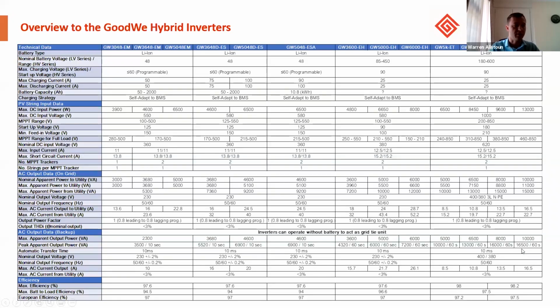And worth noting is the incredible efficiencies that GoodWe hybrid products offer, especially in the high voltage range, battery to load efficiencies. The EH series, we're looking at a peak of 96.6%, and with the ET series, 97.5%. So over the time of the plant's lifespan, you deliver many more kilowatt hours.